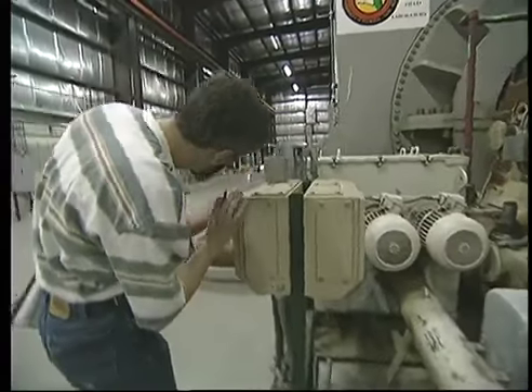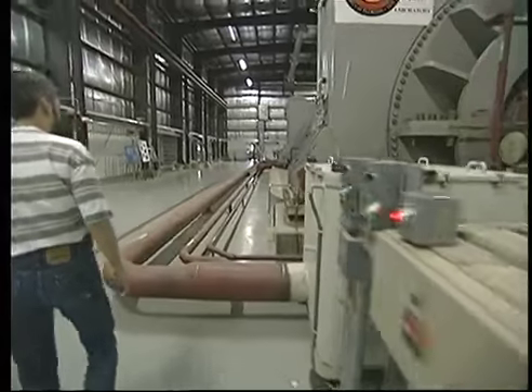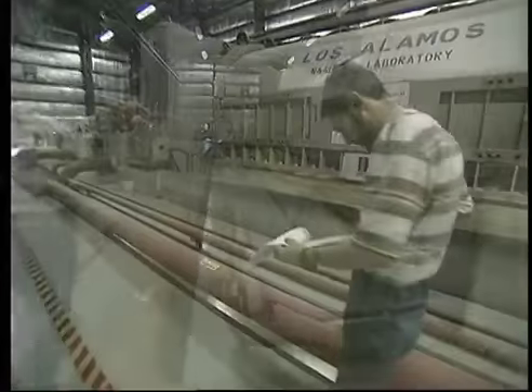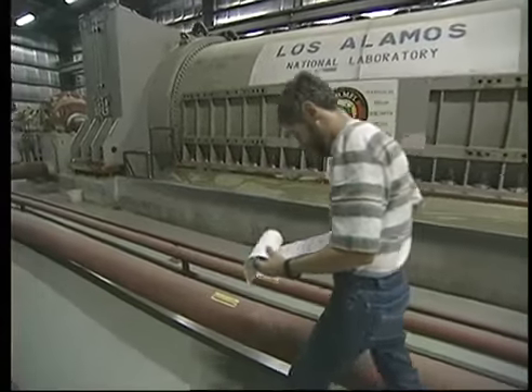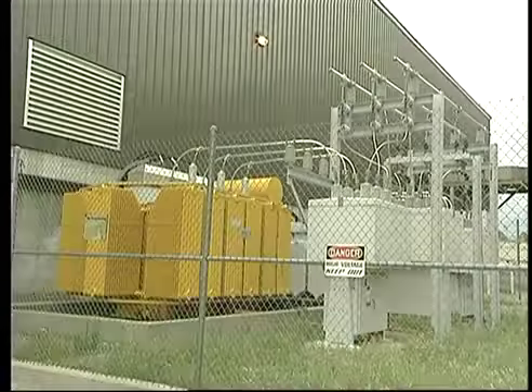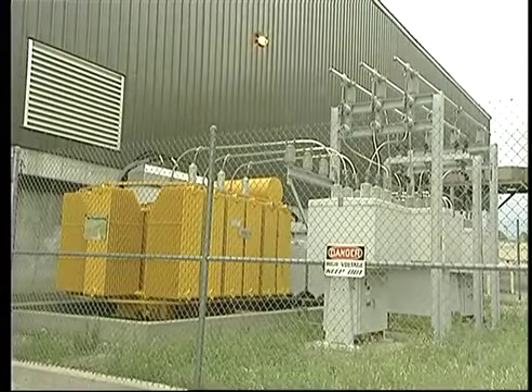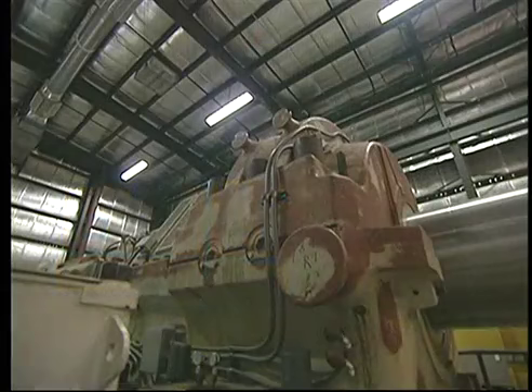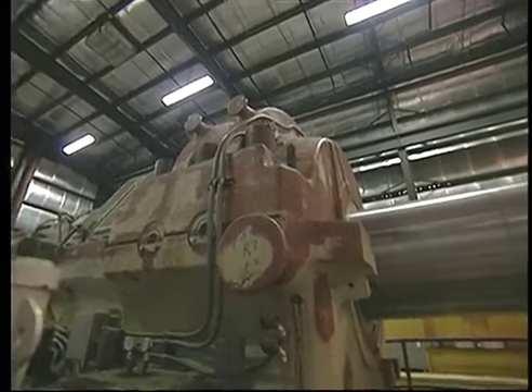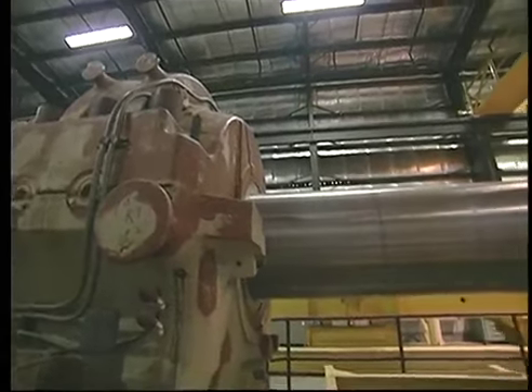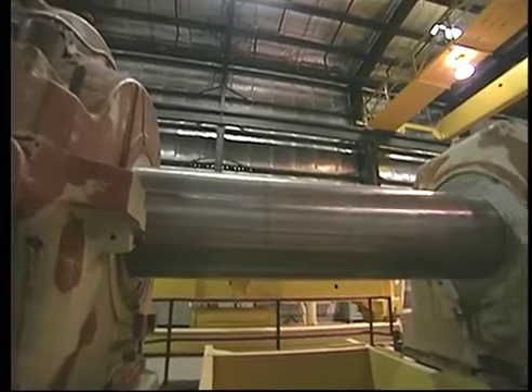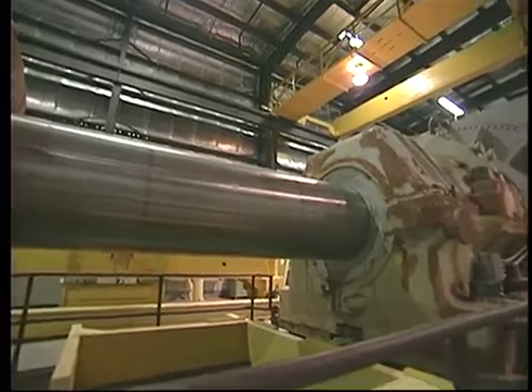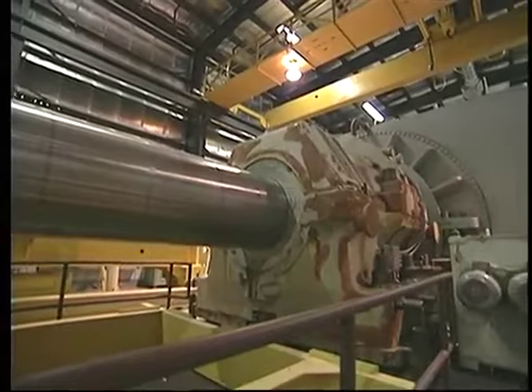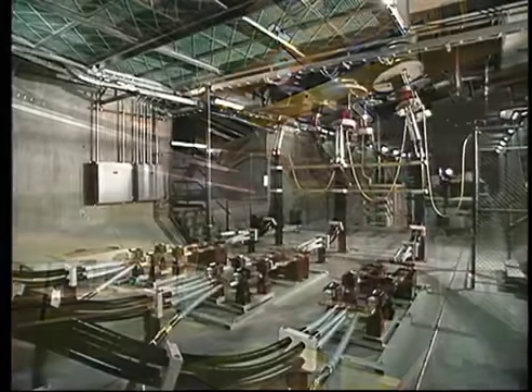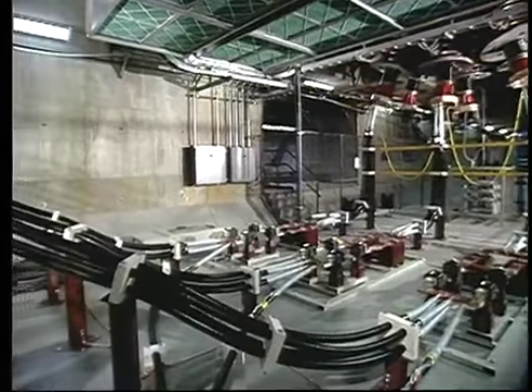The motor generator is first employed as a motor. Taking power from a commercial electrical mains, the 212-ton rotor is slowly spun up to 1,800 revs per minute in about 20 minutes. When an electrical pulse is needed to drive the magnet, the machine becomes a generator, converting the enormous kinetic energy of the rotating shaft into hundreds of megawatts of raw electrical power.